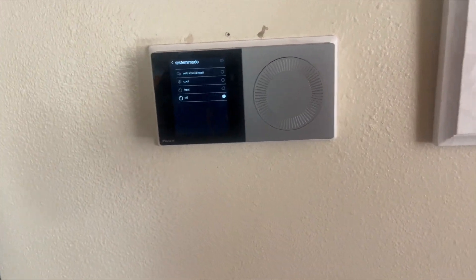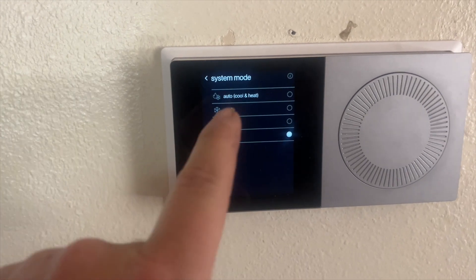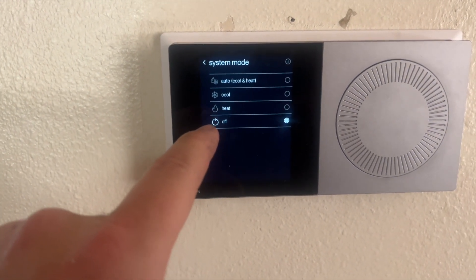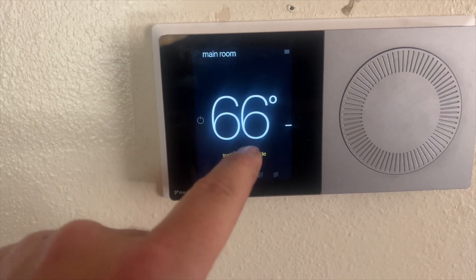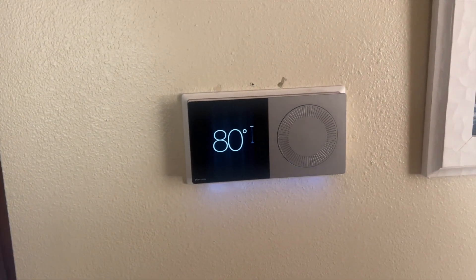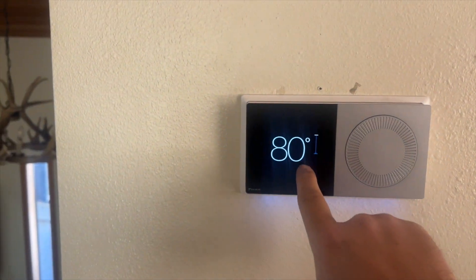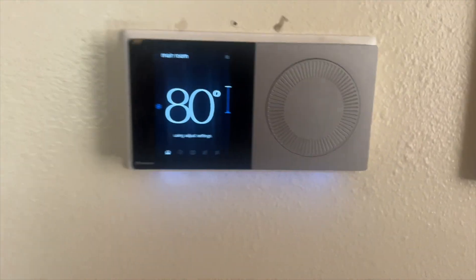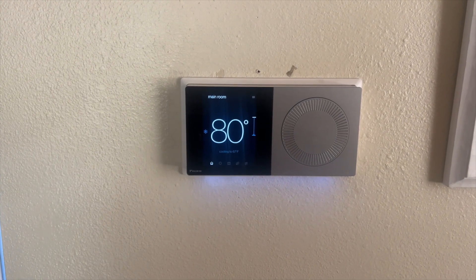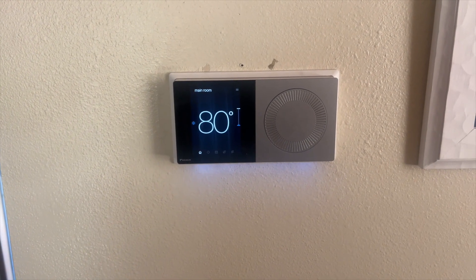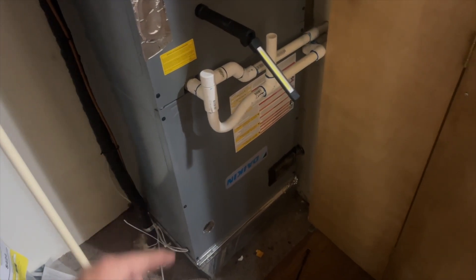It's on standby waiting for the compressor to heat up, so we might be okay because I am getting some response. Now I'm trying to see if I can get it to cool. It's 66 degrees in here, and it wouldn't run in cooling because it's too cold. I found a space heater and I'm blowing hot air at the unit to try to trigger it. According to the display it is showing cooling — it's got a little blue light — but there's no air circulation and the compressor isn't clicking on. The blower is doing something though, I can hear it clicking. Let me make sure the filter is clean.